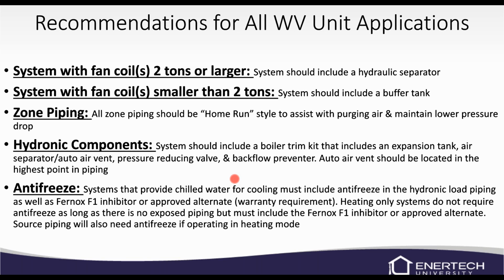I'd recommend that your zone manifolds are in the horizontal position, not in the vertical position. They don't vent air very well in those manifolds if you put them in the vertical position. Antifreeze: systems that provide chilled water for cooling must have antifreeze in the load piping. Recommend the inhibitors as well. And that's a warranty requirement now, those inhibitors or approved alternatives, the Fernox or some other brand, but for warranty purposes, those need to be installed.